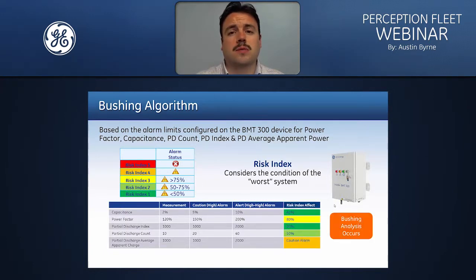So whenever the BMT takes a new measurement, we compare the measurement to the alarm levels that are set within the bushing monitor, and we then look at the risk index effect based on those measurements. You can see from the table we have here capacitance, which is measuring at 2%, with our caution high alarm set to 5% and our alert high alarm set to 10%. So the risk effect on that particular measurement is 10%. So it's seen to be in a risk index of 1.